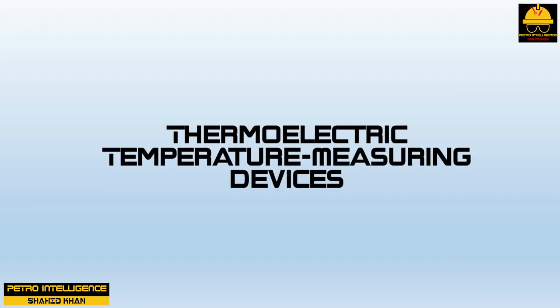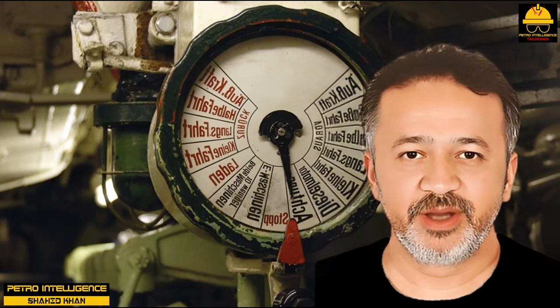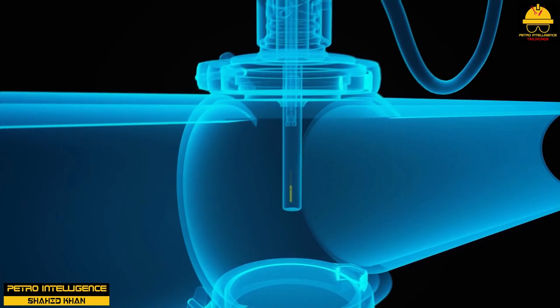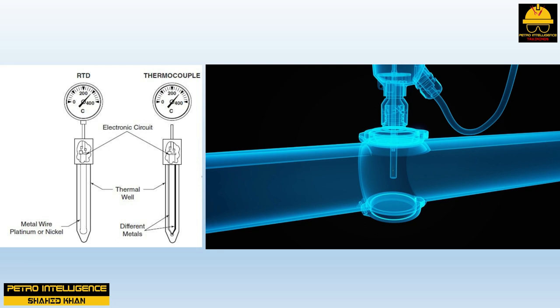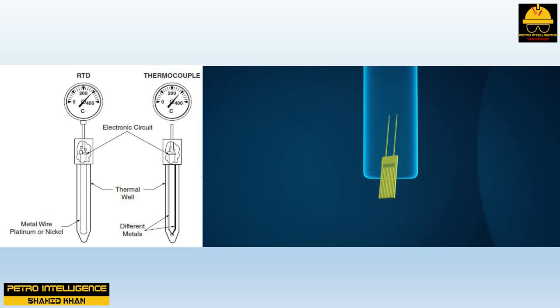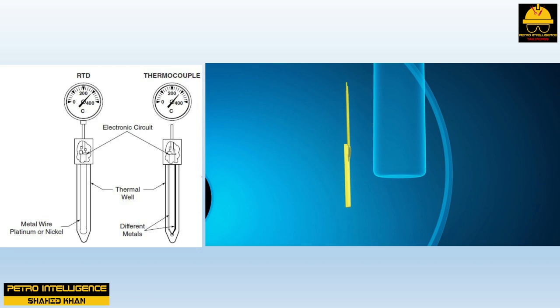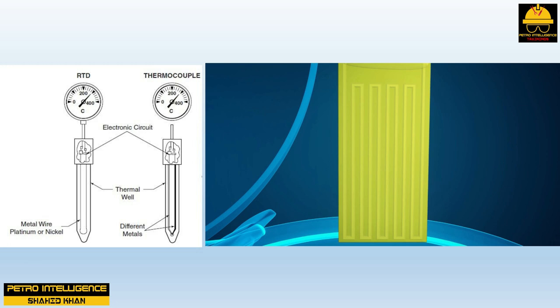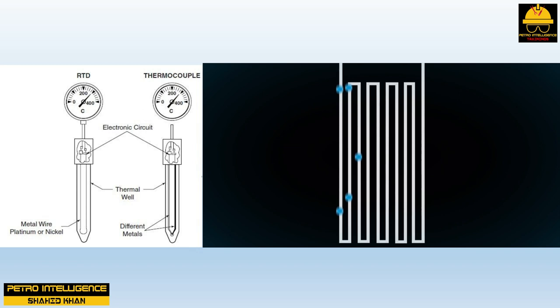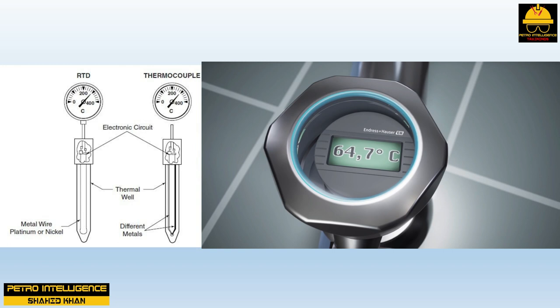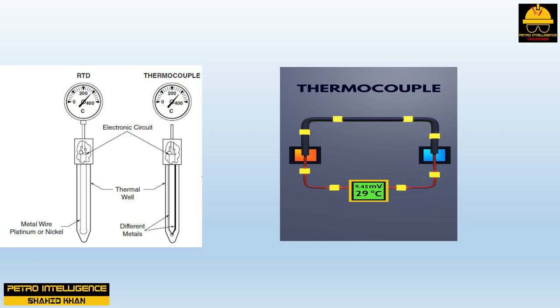The most common temperature measuring devices in the chemical processing industry are thermoelectric devices, which come in two types: resistance temperature detectors (RTDs) and thermocouples. Both are held in a thermowell, a chamber installed in vessels or piping. An RTD is composed of a small platinum or nickel wire encased in a rugged metal tube; the electrical resistance in the wire is influenced by changes in temperature. Temperature changes in an RTD are sensed by an electronic circuit and directed to a temperature indicator.